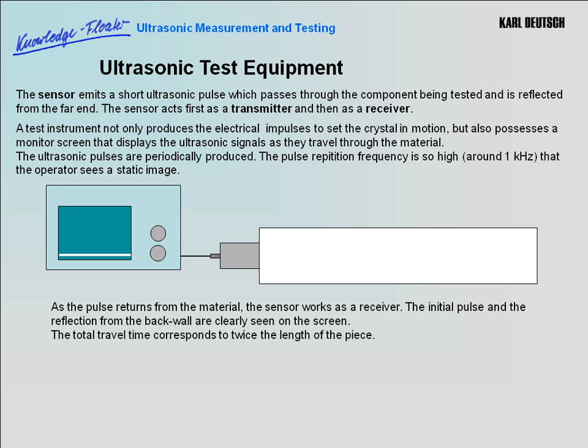Ultrasonic test equipment. The sensor emits a short ultrasonic pulse which passes through the component being tested and is reflected from the far end. The sensor acts first as a transmitter and then as a receiver. A test instrument not only produces the electrical impulse to set the crystal in motion, but also possesses a monitor screen that displays the ultrasonic signals as they travel through the material.